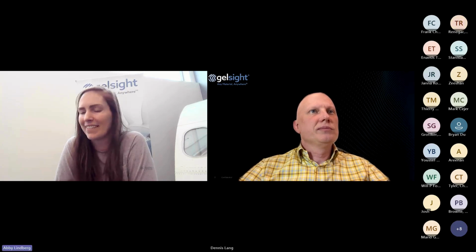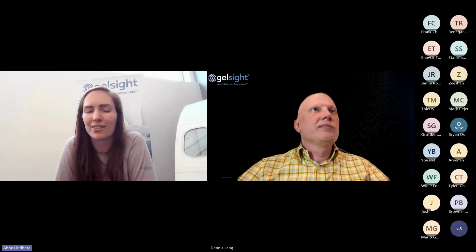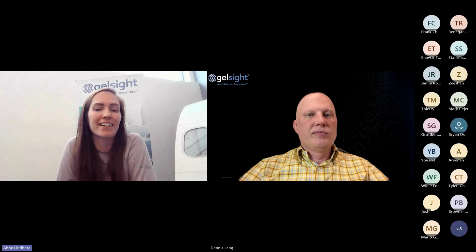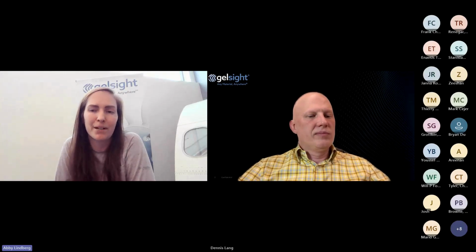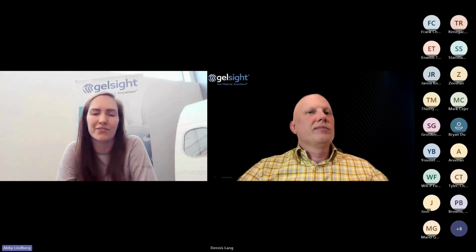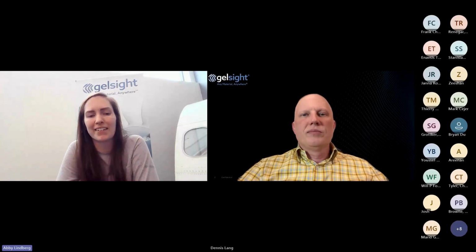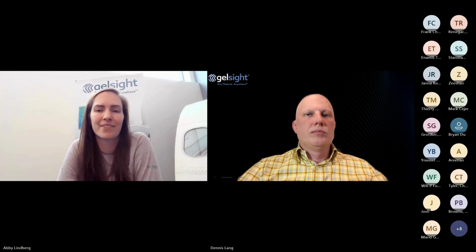Yeah, and I can add something else to that too. We also find a lot of people use our system in areas of known defects. They might not see a defect in it currently, but they know that that's a common spot for defects to occur. So it might not be scanning the entire part necessarily, but it's more than just where they find a defect. They are also spot checking common stress points as well.